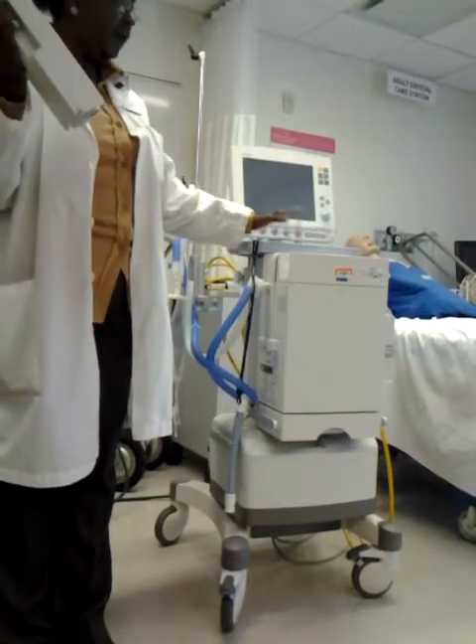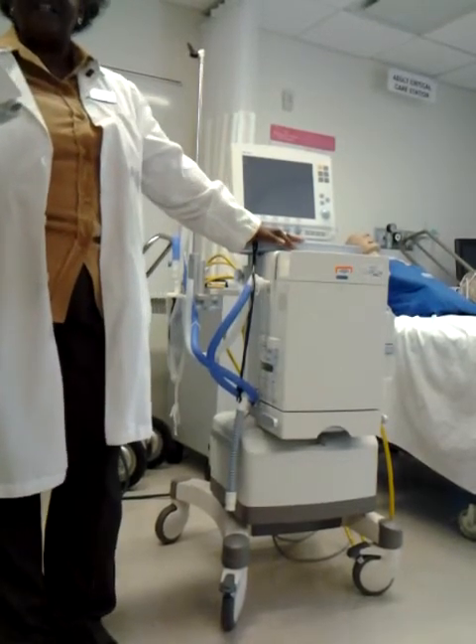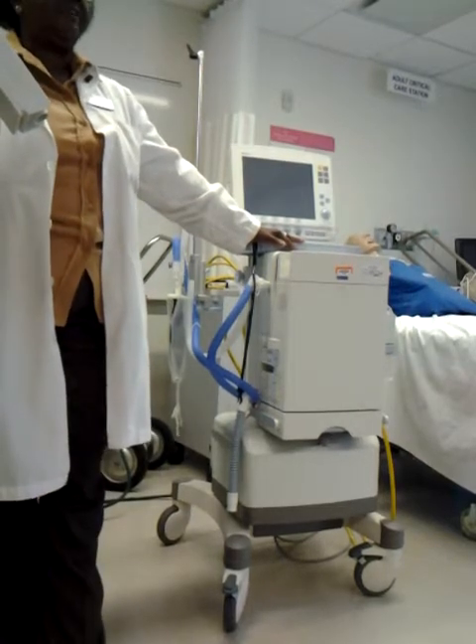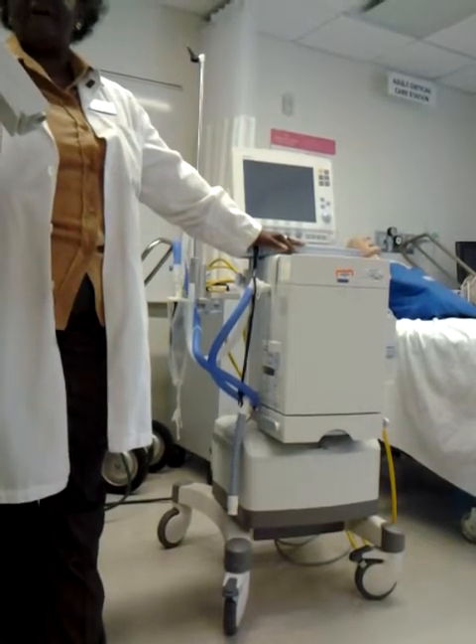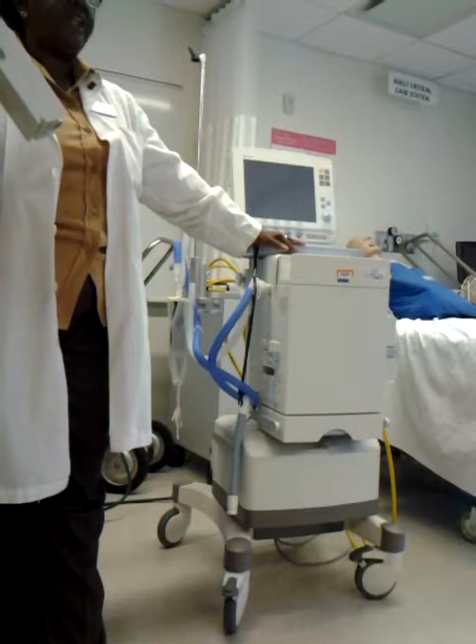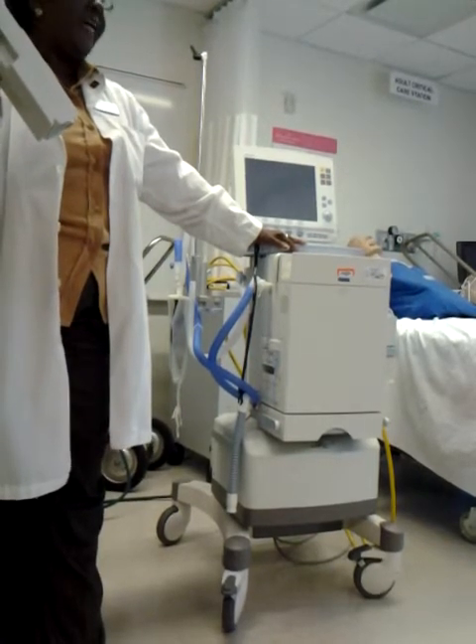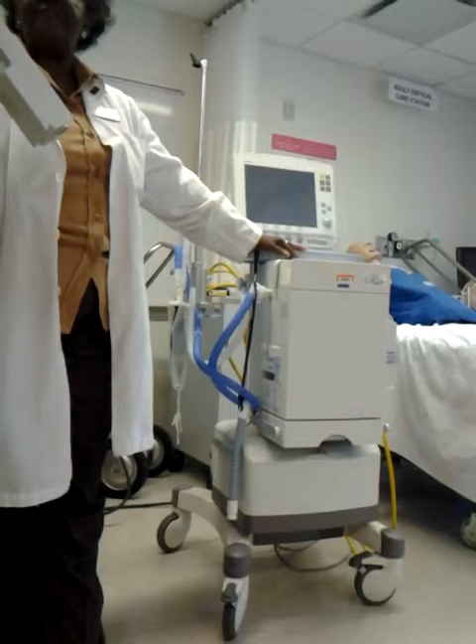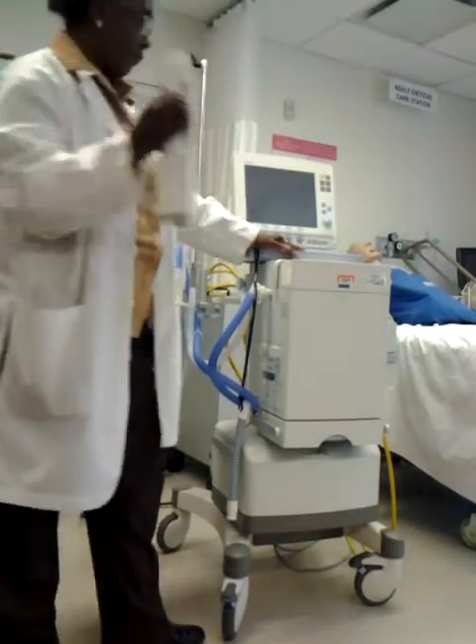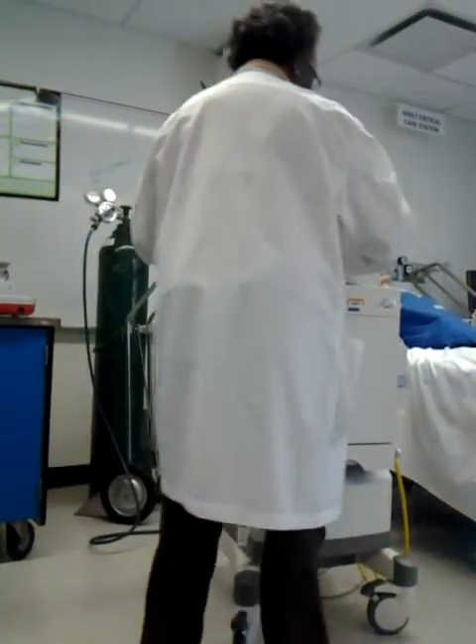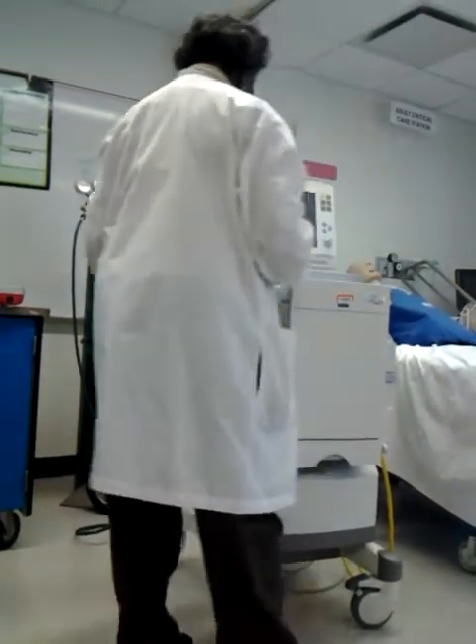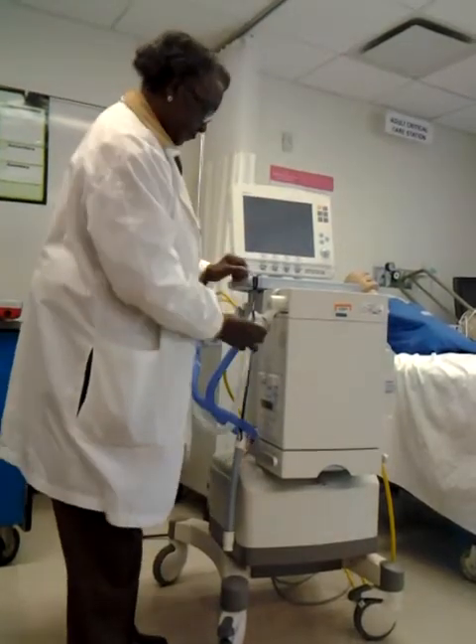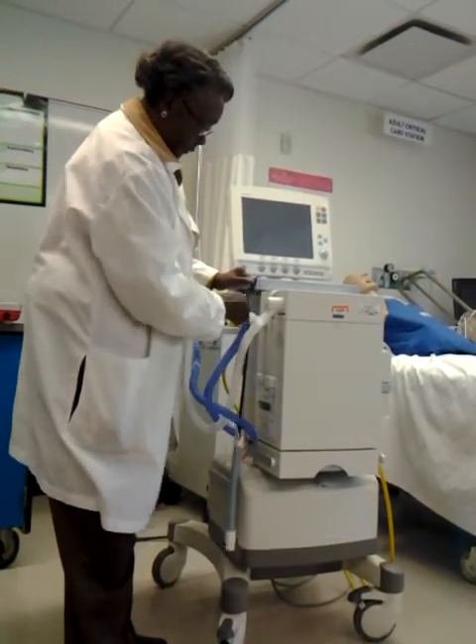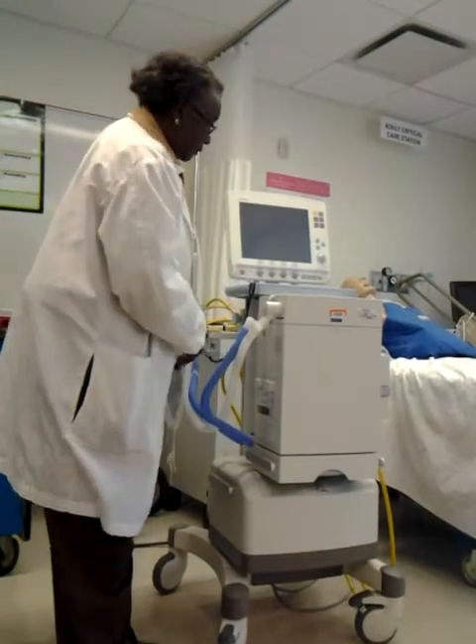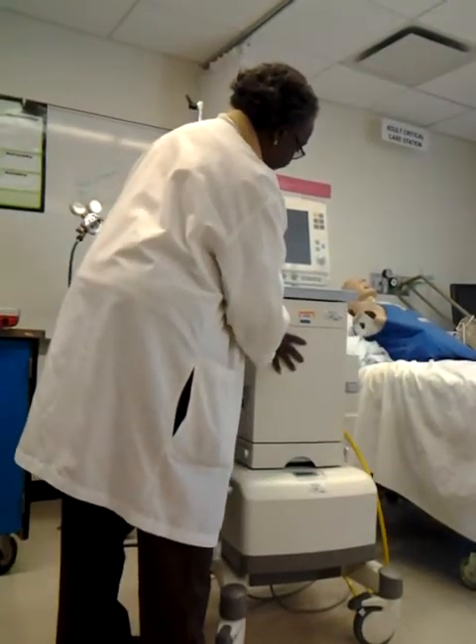You also have a built-in oxygen analyzer in here. Right now we have a galvanic cell, and they're not good for very long. I'm hoping the guy's going to come back and put a different kind of analyzer in here that will last a little longer. It measures on the inspiratory limb the FiO2 going to your patient. Part of the checkoff, of course, will be taking this thing out and putting it back together. It's very simple. I really should have a filter on here, but it just got taken off. And you saw how that came out.